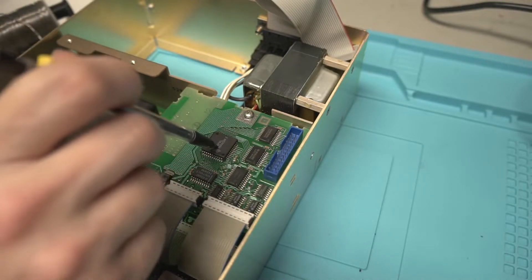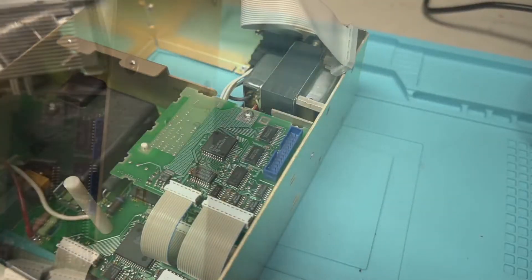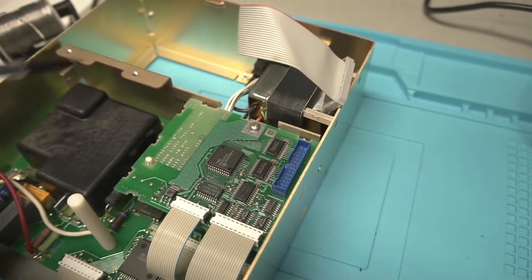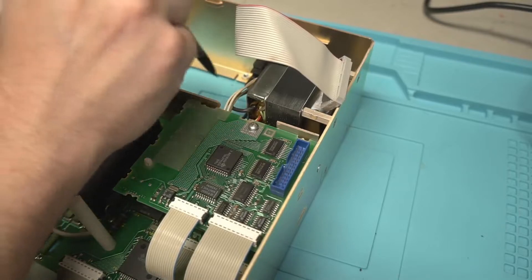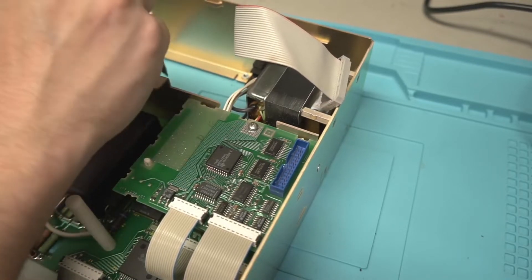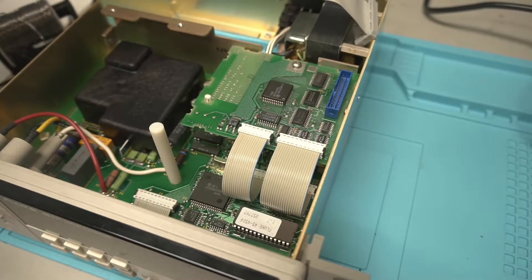This board is an optional board on these for the IEEE 488 standard. So that is what this daughter board is here. This blank space over here is for another option. There's an option for a rechargeable battery pack that goes in there. So that way this thing can run off of the batteries. I think it'll run off the battery for like three hours when it's a good battery and it has a 30 minute warning light. So that's kind of the main thing.